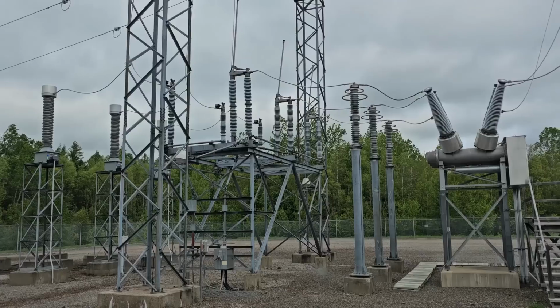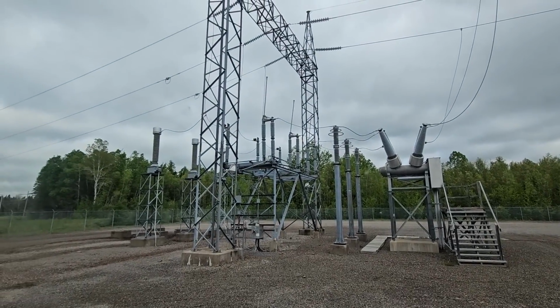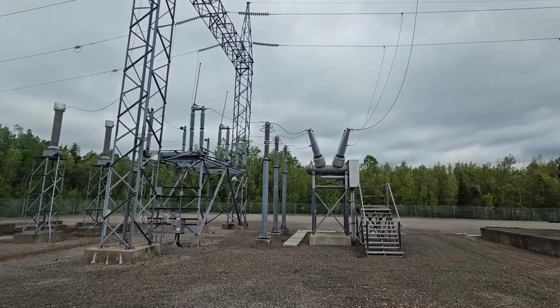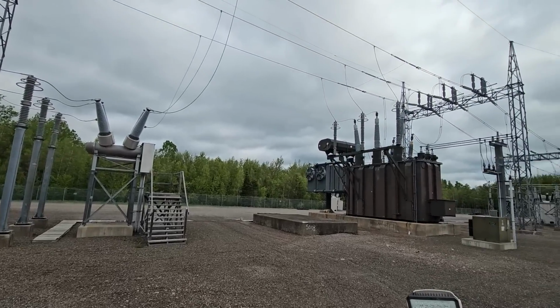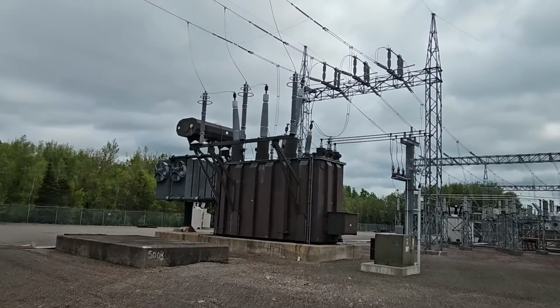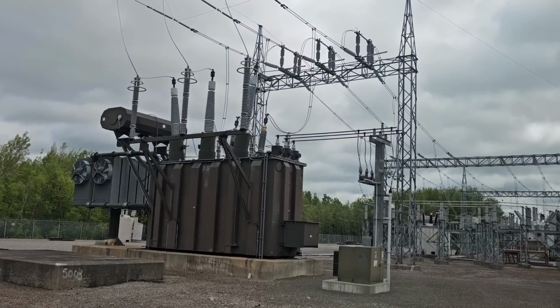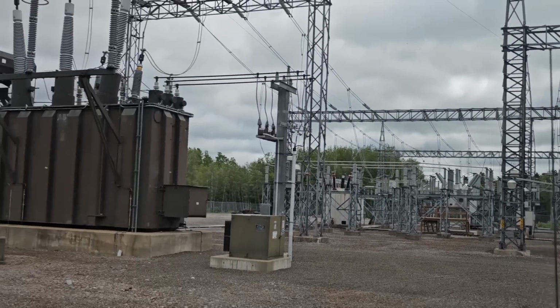We have the low voltage and high voltage substation techs that mostly look after this stuff, and our transmission line crews. But we've got a transmission crew out on the line taking work permit right now, so I'm doing the switching for them. Might as well take you guys across the yard and show you the switching that we just did. So the guys are going to be working on a 230,000 volt system. This 230 kV line off to the left feeds into our terminal through that power transformer right there, and that's a 230 kV to 138 kV transformer. That feeds that entire 138 kV switch yard off to the right.